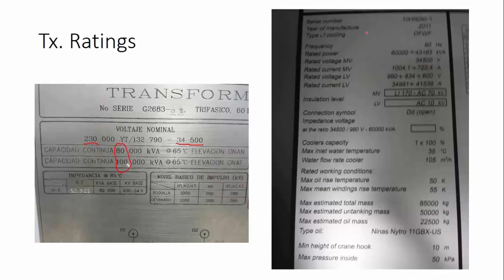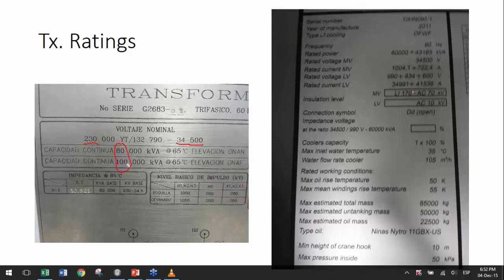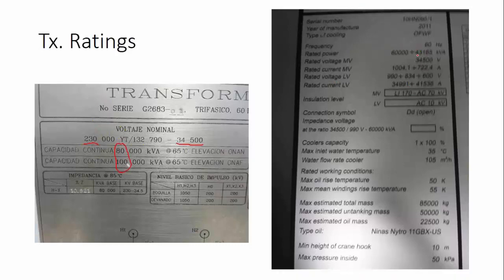And this is the rating for the electric arc furnace transformer, which you can see can operate from 43 MVAs up to 60. The range can vary quite a bit because, depending on how high the arc is, the power of the furnace varies a lot. So it can vary from 43 to 60, quite a variation. And the low voltage can go from 600 volts to 990, almost 1000, and it depends on how long you need the arc to be, and on the part of the melting process that you're in. So this is a typical electric arc furnace transformer.